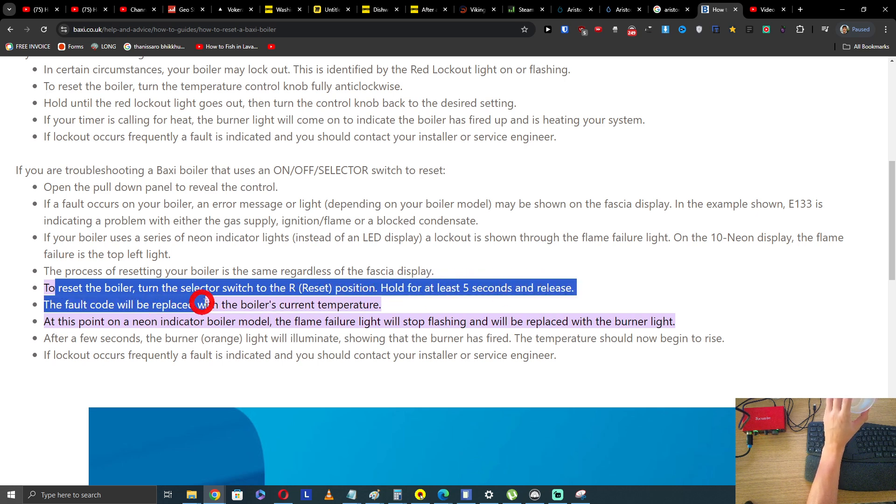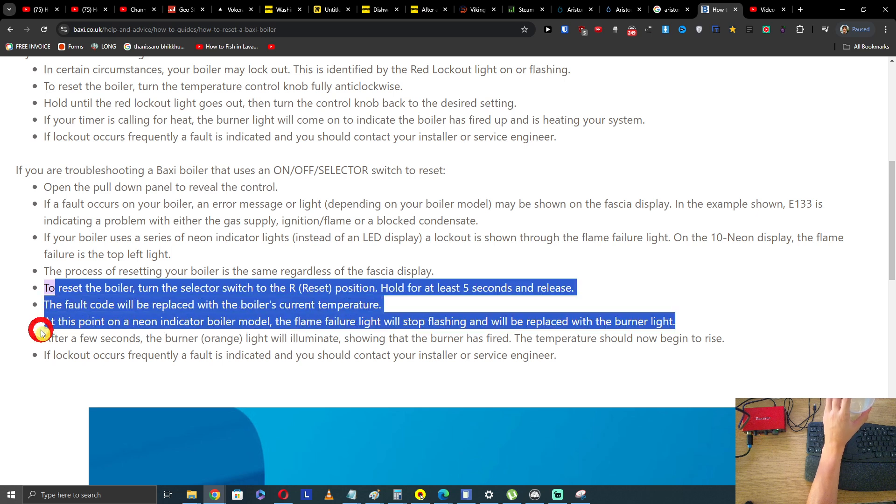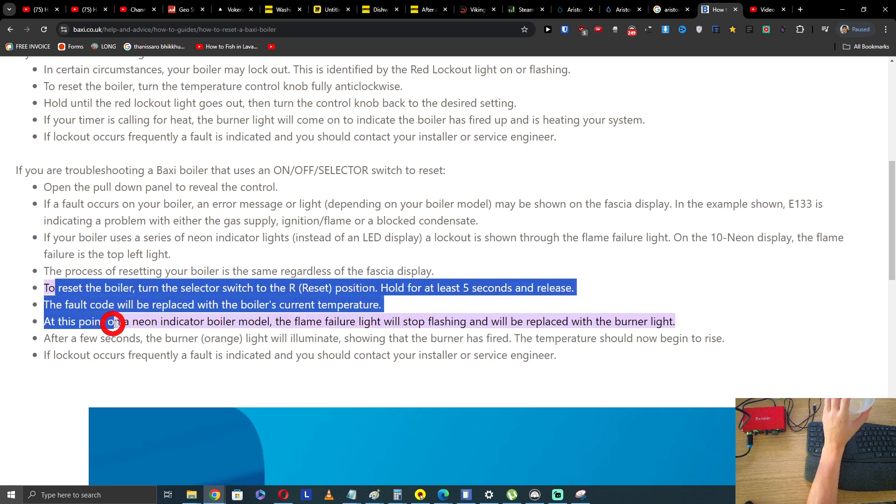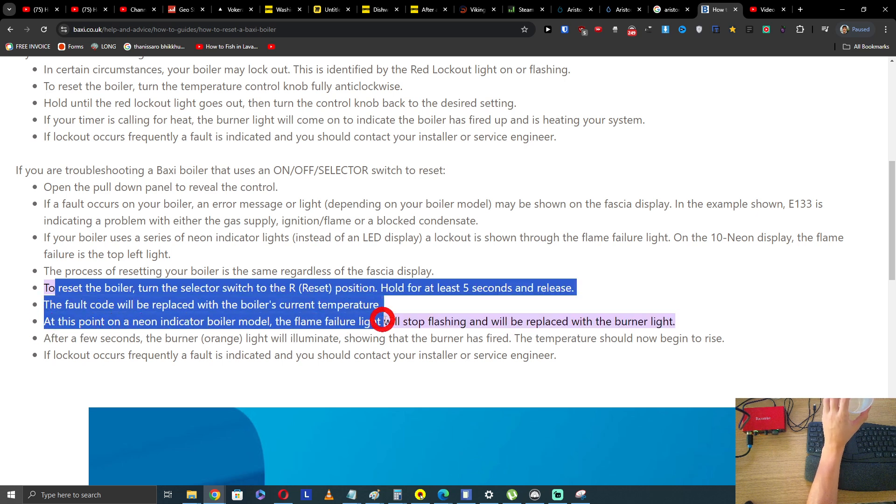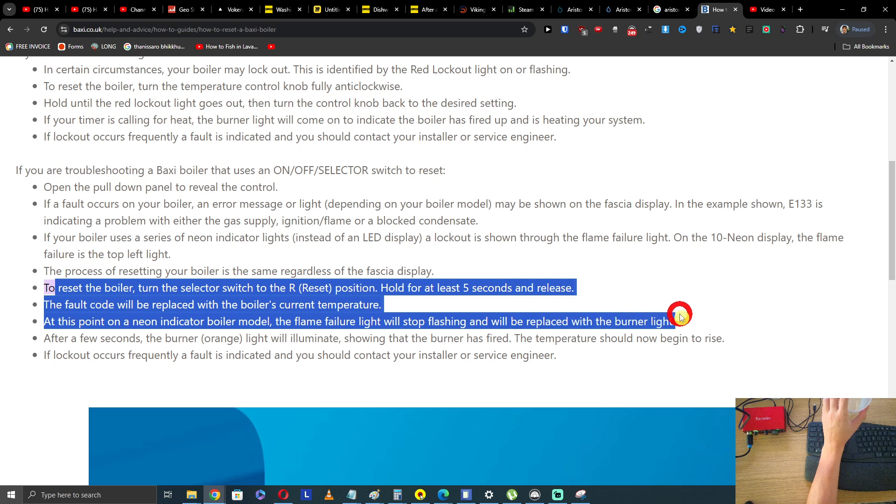The fault code will be replaced with the boiler's current temperature. At this point on a neon indicator boiler model, the flame failure light will stop flashing and will be replaced with the burner light.